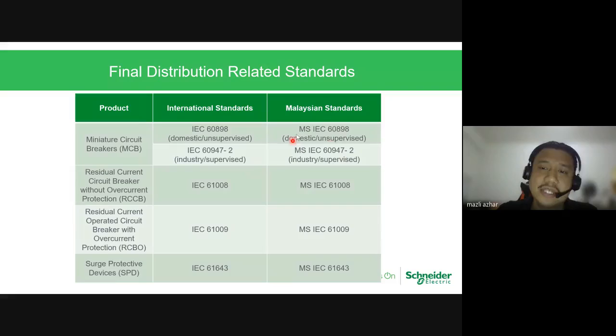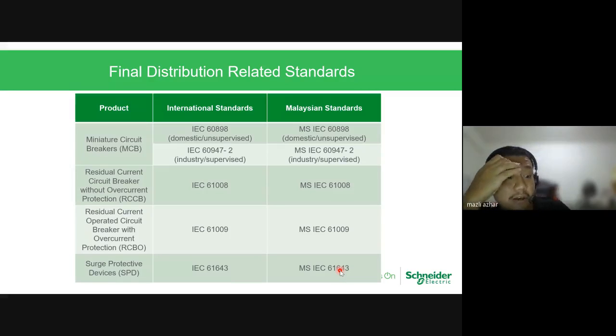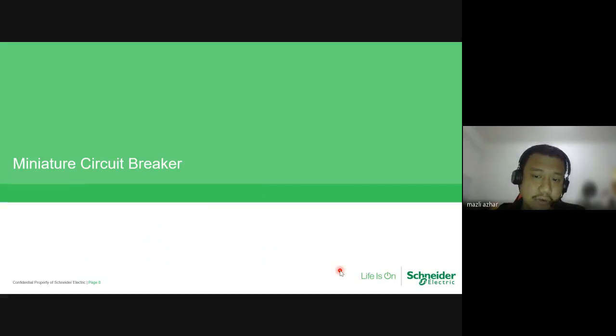So for MCB, there are two standards: 60898 for domestic and unsupervised, as I mentioned, those who don't have technical information or anything at all about electricity, and 947 for industry and supervised, whereby you will have a technician, a wireman, a chargeman or an engineer who can monitor and ensure that protection is achievable 24 hours, 7 days a week, 365 days a year. And then you will have RCCB and RCBO, a combination under RCD, as I mentioned. So 61008 for RCCB, 61009 for RCBO, and then SPD 61643. Why am I showing standards? Because when you graduate and go to the market, standards will come into play whenever you want to do anything in design or finalization. Everything we refer to the standards. So we go for the first one, the miniature circuit breaker.